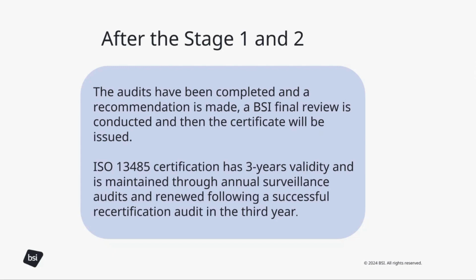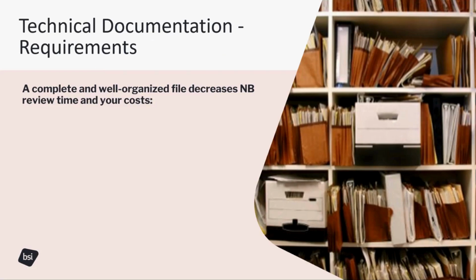The ISO 13485 certificate is valid for 3 years, but during year 1 and year 2, we will do a surveillance audit for this certificate, and in year 3, this is when we will re-audit and do the renewal. So that's why the 3rd year is considered the recertification year. So you have the first-year audit, year 1 and year 2 surveillance, and year 3 recertification, and then you start the cycle again. If you do it in parallel with the MDR, the certificate is valid for 5 years. This is when we will assess the technical documentation, in case you apply for the MDR.